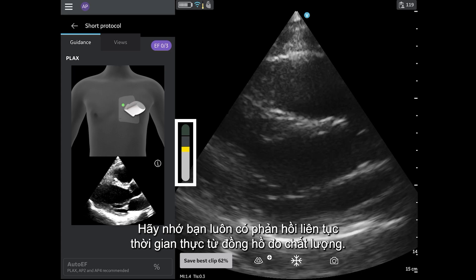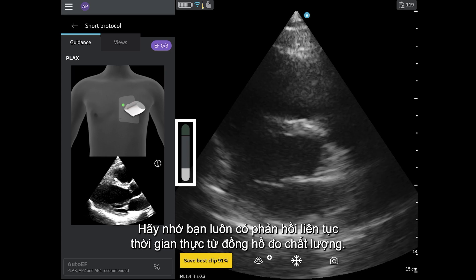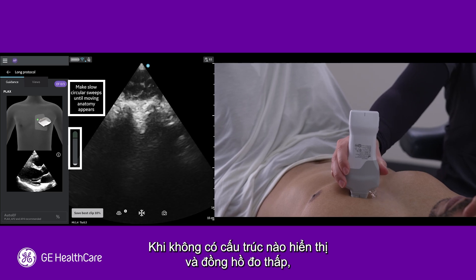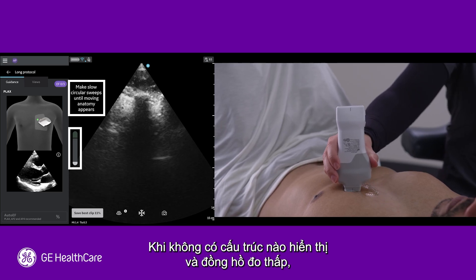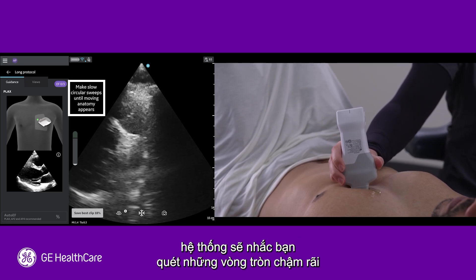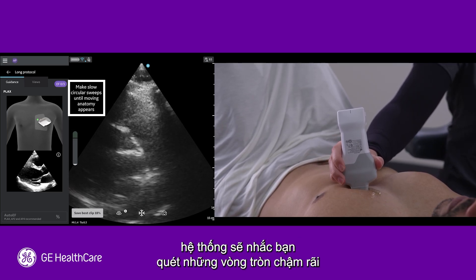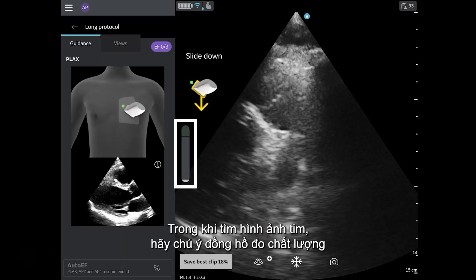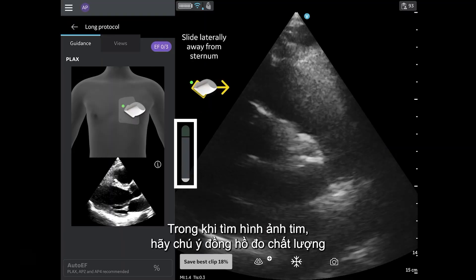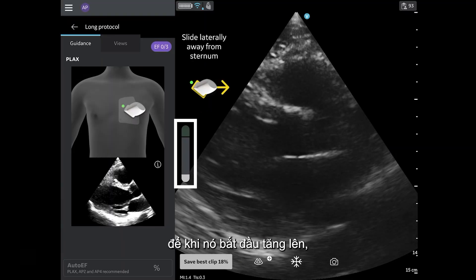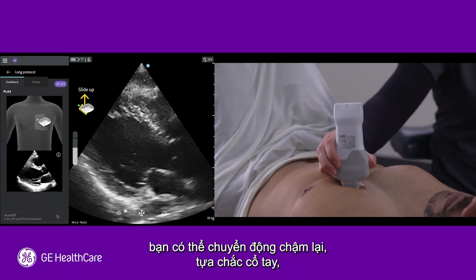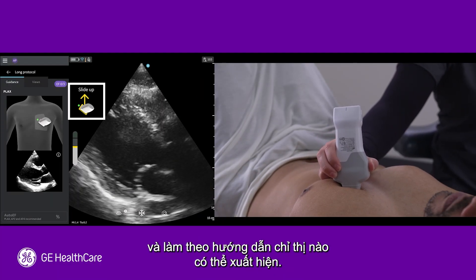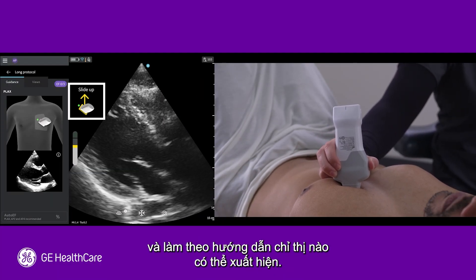Remember you always have continual, real-time feedback from the quality meter. When no structures are visible and the meter is low, the system will prompt you to make slow circular sweeps until moving anatomy appears. While searching for the heart, pay attention to the quality meter so that when it starts to go up, you can slow your movements down, stabilize your wrist, and follow any prescriptive guidance that may appear.